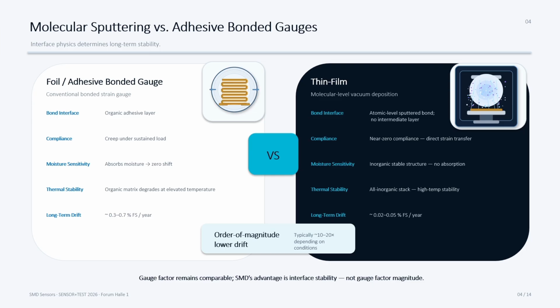This slide is about the thin film design choices: glue versus sputtering, depending on what we want to use. An adhesive bonded foil gauge uses an organic layer between the gauge and the metal, and that organic layer creeps under sustained load. It can absorb moisture, and thermal stability becomes an issue.